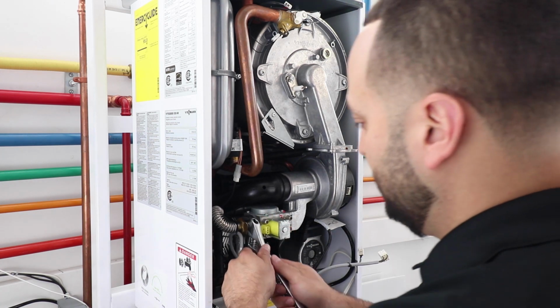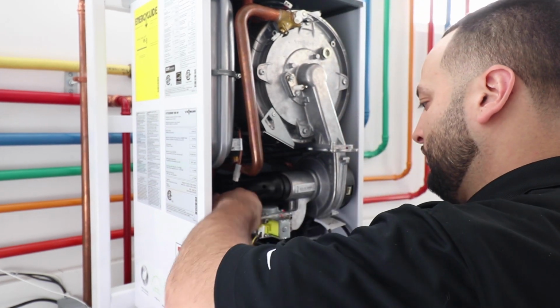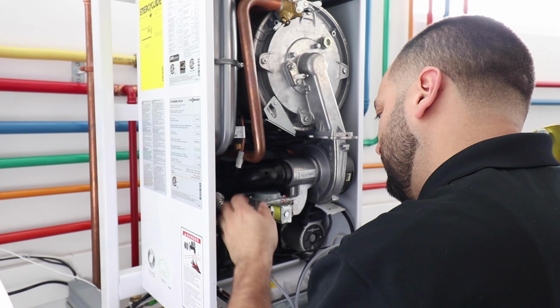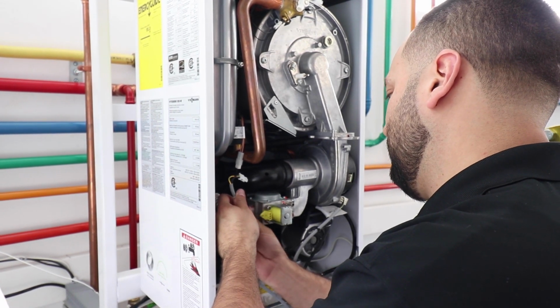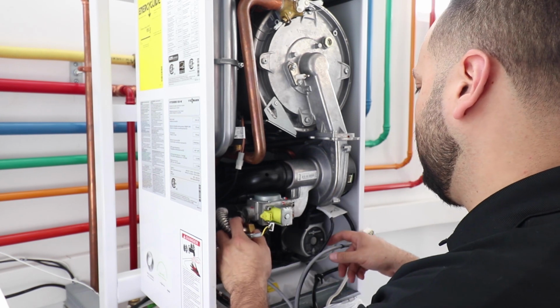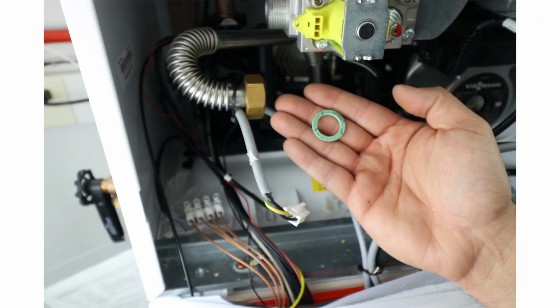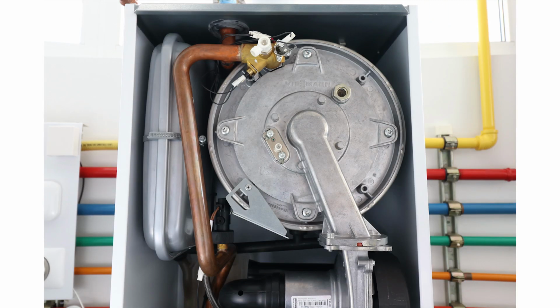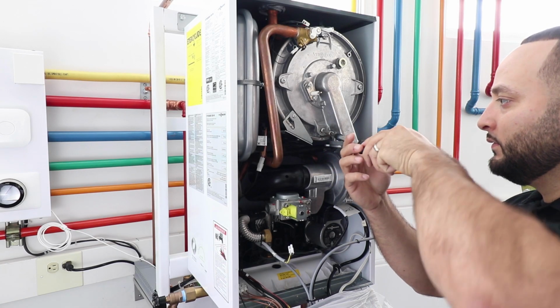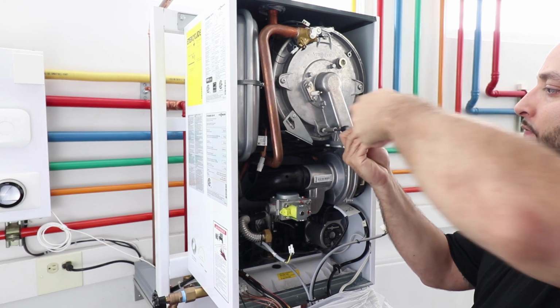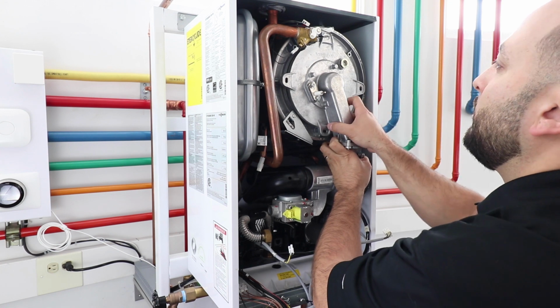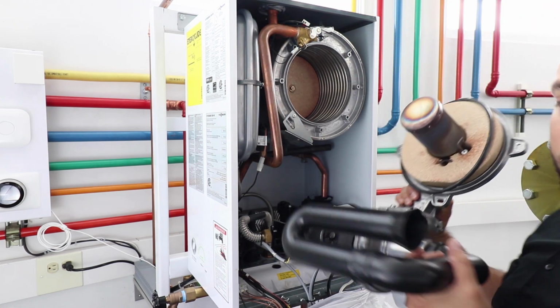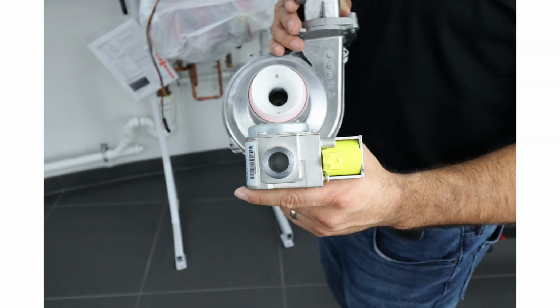Next, we'll remove the gas line connection. Be sure to retain the fuel connection pipe gasket. Next, we will remove the 4 Torx head screws to gain access to the heat exchanger. Inspect the gas valve inlet screen for debris.